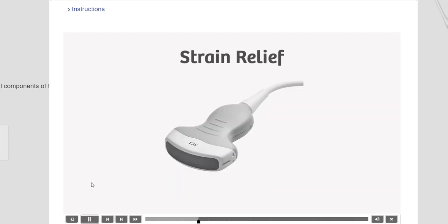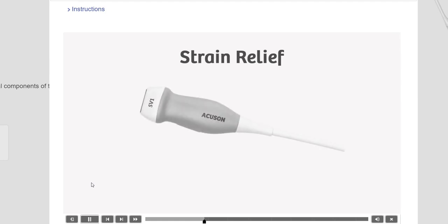The strain relief is made of lightweight material, making holding the transducer and cable more ergonomic. The strain relief is a common location for damage. If the cable accidentally wraps around an external component on or near the ultrasound system and the system moves with some force, the strain will uncouple from the transducer housing.